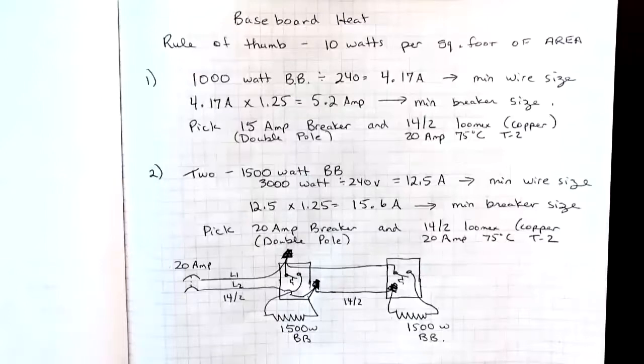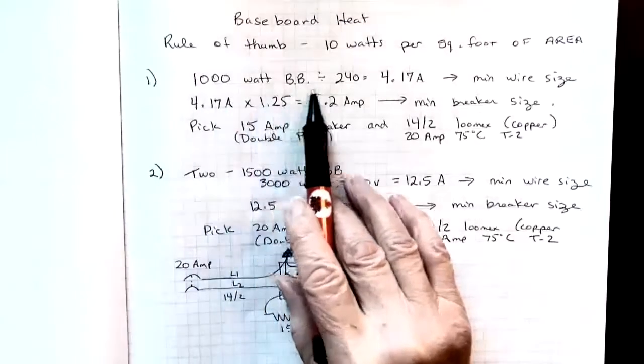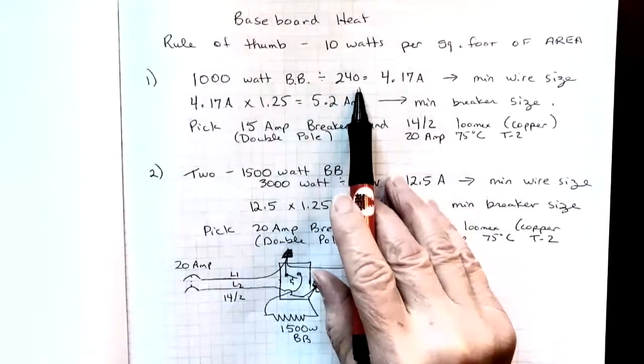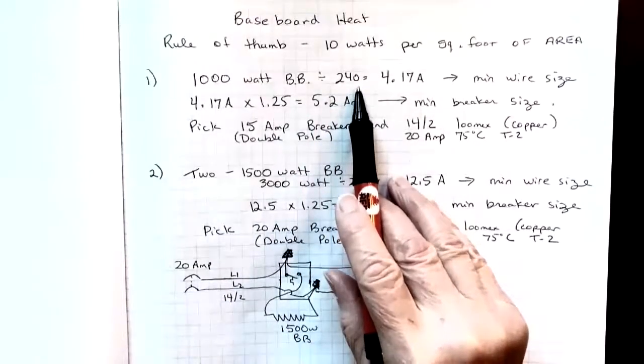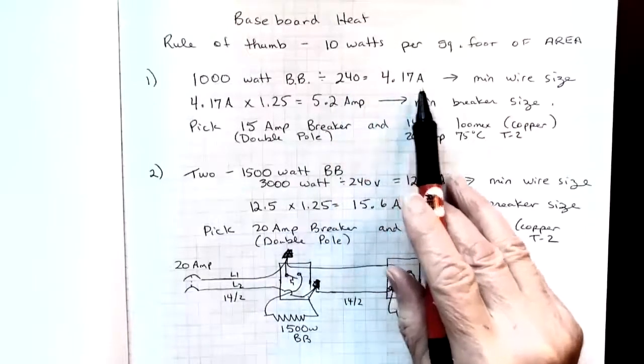Our first example then would look at that thousand watt baseboard heater. If that was the only thing on that circuit, say you were doing the renovation and adding a baseboard heater to this room, we would take 1000 watts divided by 240. Most of our baseboard heaters are 240, although you can buy 120 volt heaters as well, in which case you would have to divide it by 120 volts. That gave me 4.17 amps.